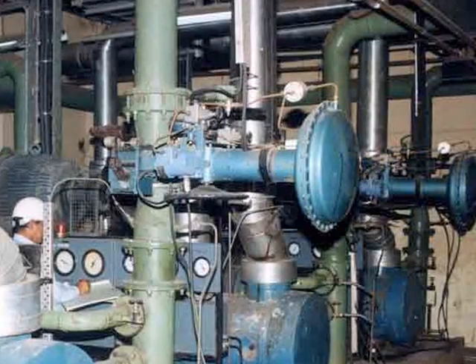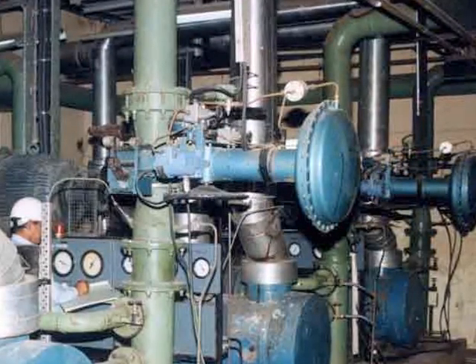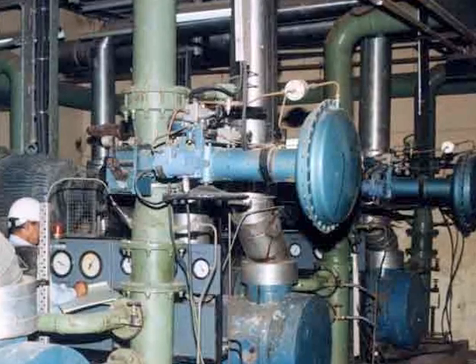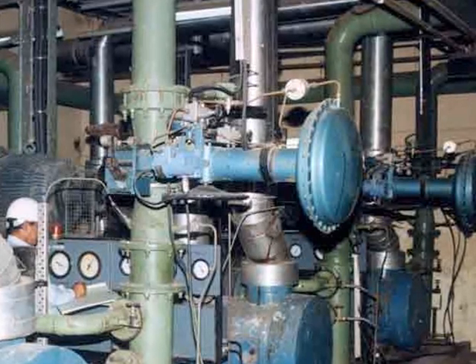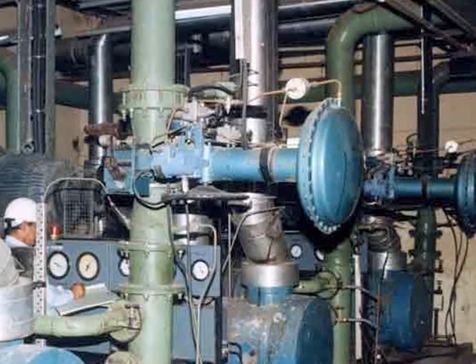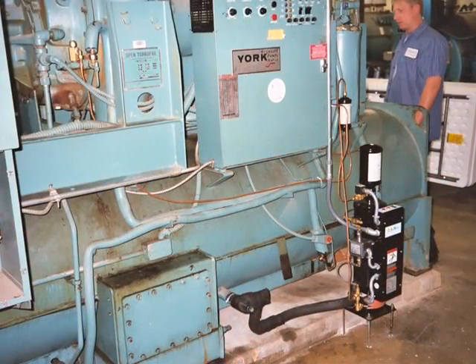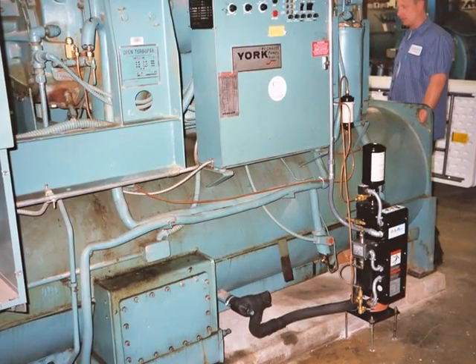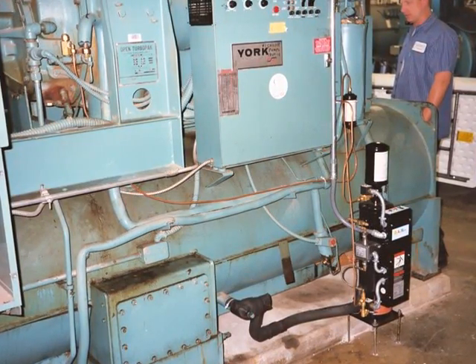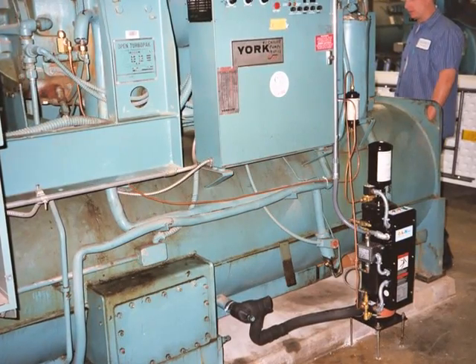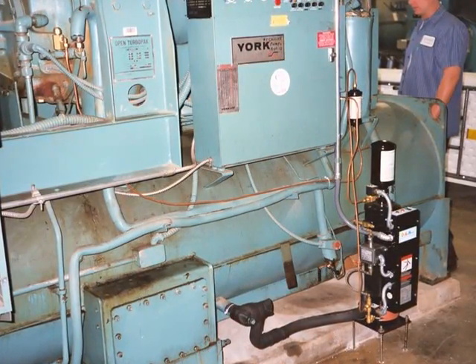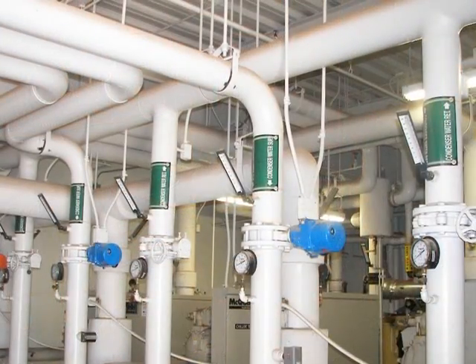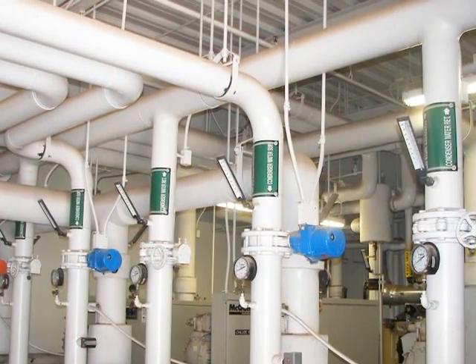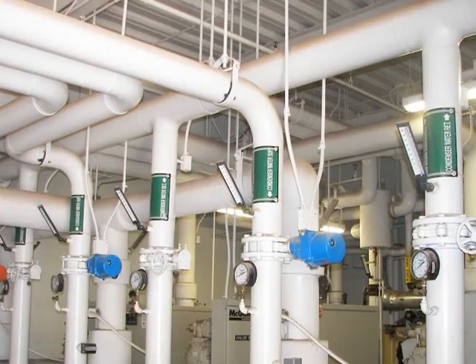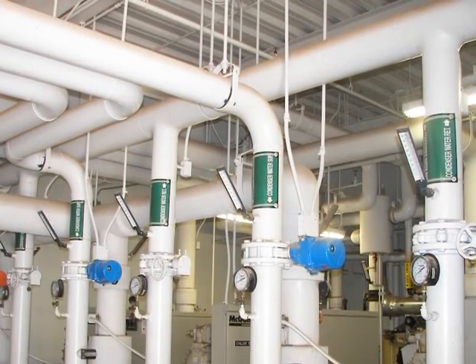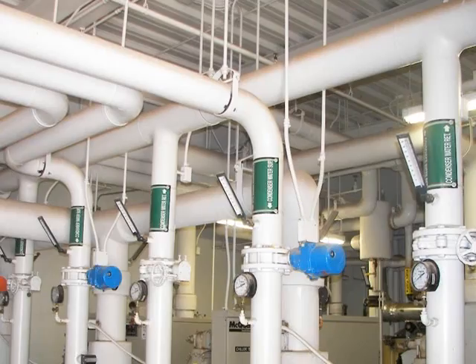Once oil gets into the chiller's refrigerant, it's very difficult to get it back out. In the past, about the only way an oil-logged chiller could be fixed was to either remove and distill the refrigerant or replace the charge with virgin refrigerant. In either case, it was a very expensive process and it required a considerable amount of downtime. As you are aware, most centrifugal chiller applications simply cannot afford to have a chiller down. Also, utilizing the past methods of cleaning or replacing the refrigerant charge, the fix was only temporary. The minute the chiller was placed back into operation, oil contamination began all over again.